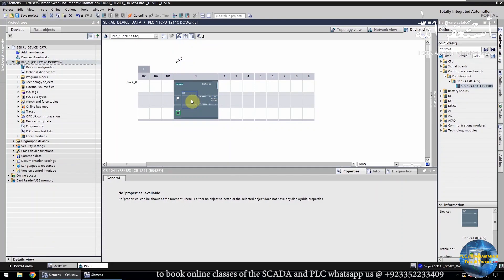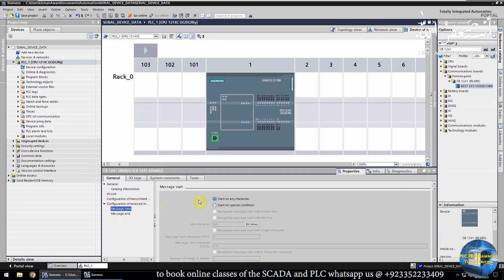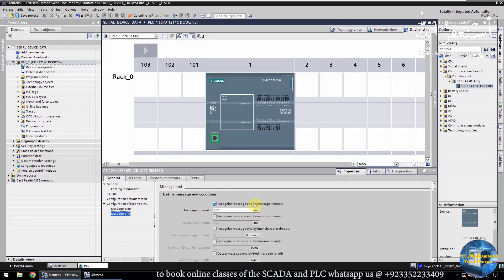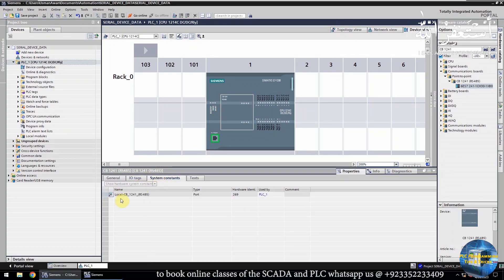Now the communication module is added into the project. If we open the received message configuration, the message can be started with any character, and if there is no message for 200 milliseconds, it will be considered as the end of the message. If we open the system constants, we can see the hardware identifier for the RS-485 port, which is 269. We will use this port number later in this project.